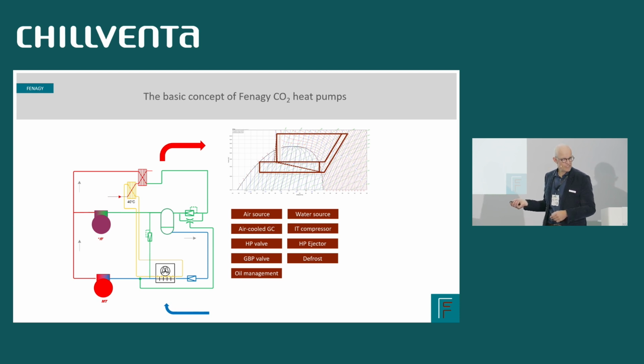Now we talk about air source heat pumps. So this is the energy collector, the evaporator, taking the heat from the ambient air. The MT compressor compresses all the way up to the gas cooler, rejecting the heat into the district heating system, back into the receiver through a high pressure valve. But of course we have ejectors, so most of the motive flow here is going through the ejector.